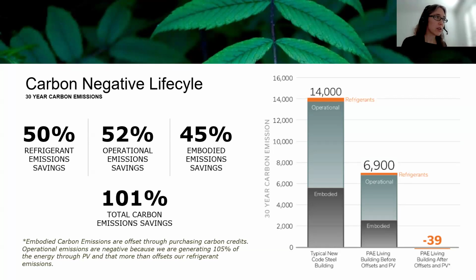We also strove to reduce refrigerant emissions by strategically locating that refrigerant piping. We had a single chase going down, basically minimizing the amount of refrigerant piping in the building, converting from refrigerant to water, that sort of thing. We also used brazed fittings, which are shown to leak less.